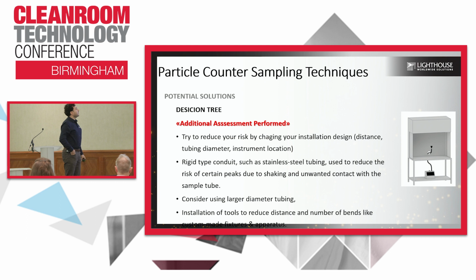Fine, additional assessment performed. Exactly the same thing. We will start with the installation design, how we can evaluate it, how we can change our system design, how we can locate the particle counter at the nearest point of our system. And rigid type conduits, such as stainless steel tubing, are used to reduce the risk of certain peaks due to the shaking and unwanted contact with the sample tube.